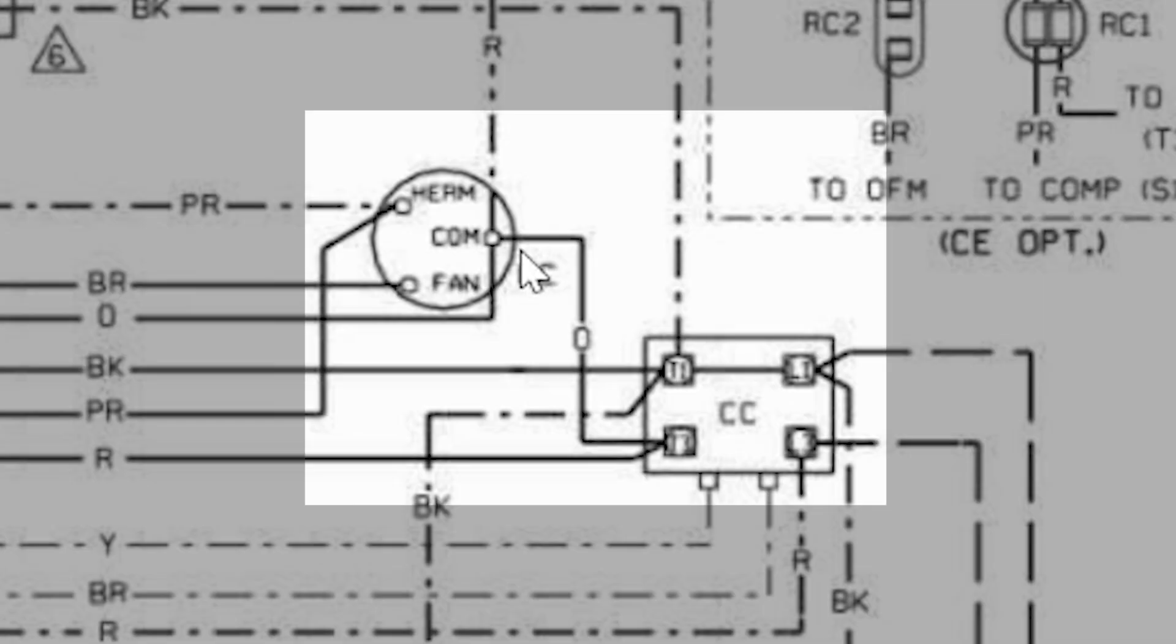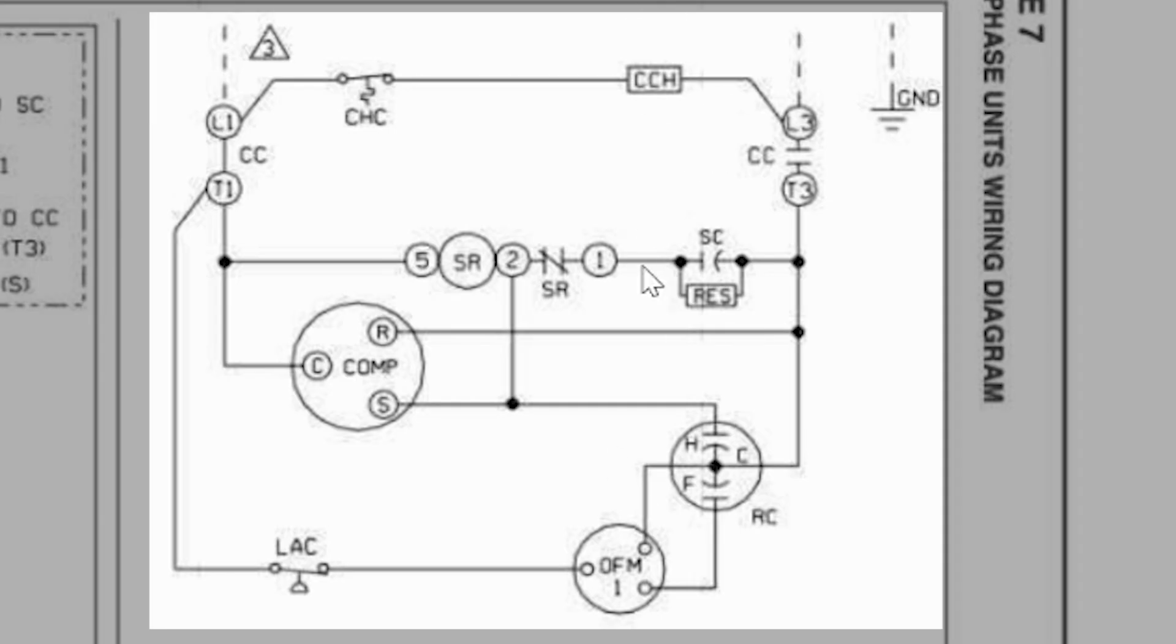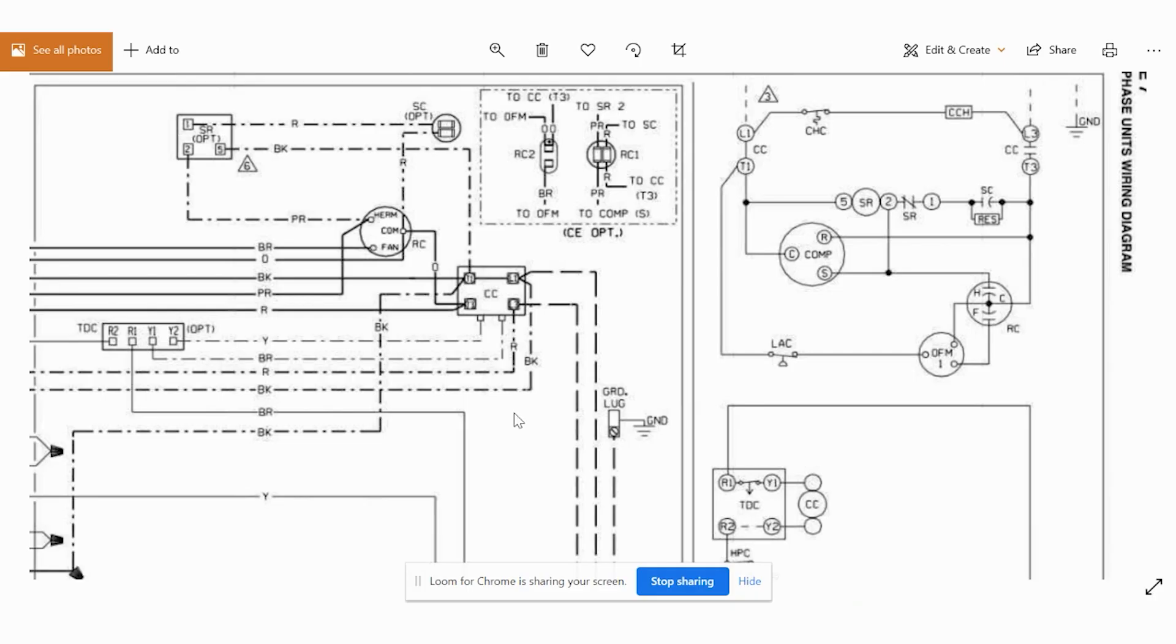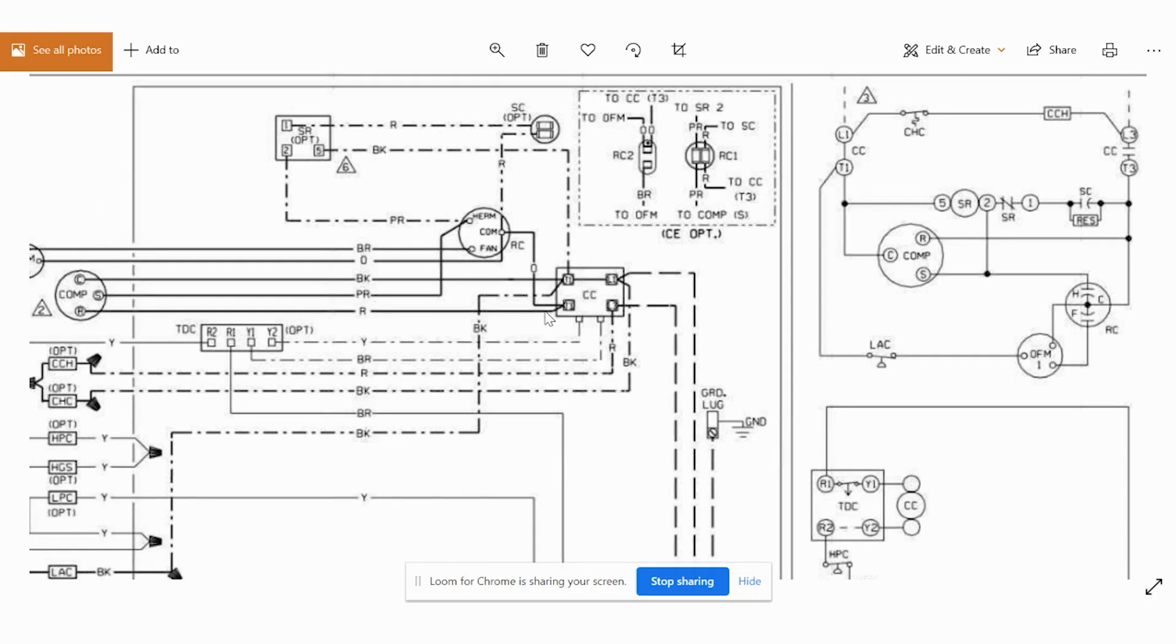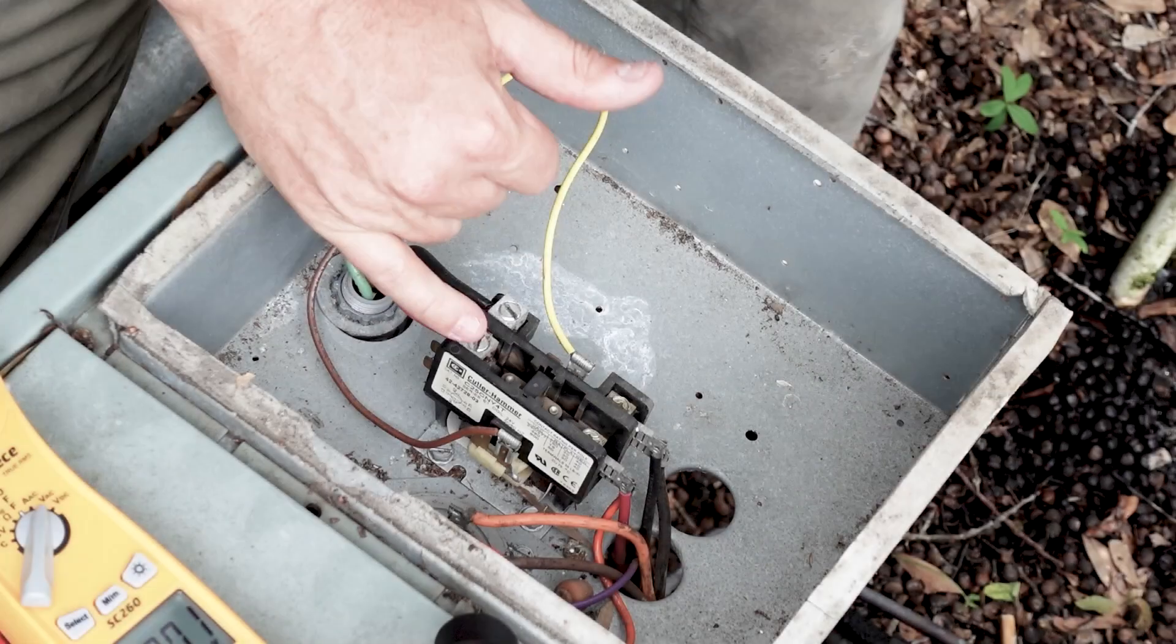We have O, which is the run winding. If you look at O, O is orange. It connects to common, which then is also jumpered over to our contactor. So those are these two wires. And you can see here, this doesn't really show exactly how they're connected. It just shows that they are connected. When you get over here, it's going to show specifically where the wires are connected and what the colors are.